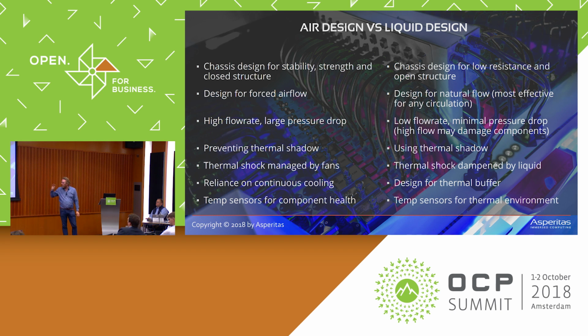Temperature sensors in air are very much used to determine component health. In air, if a memory module becomes defective, you may notice it because of the temperature increase of that specific module. Inside liquid, due to its high thermal capacity, you may not see any temperature increase at all, but you can use that temperature to get an idea of the environment temperature around that same memory module.